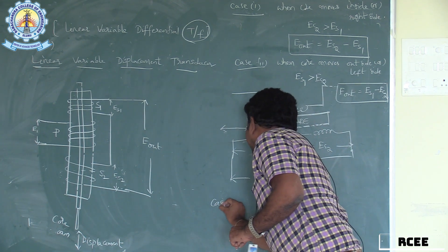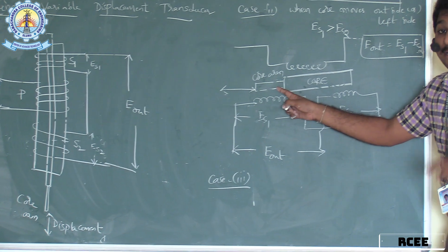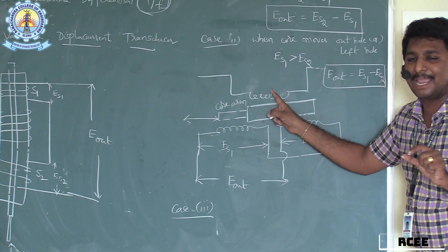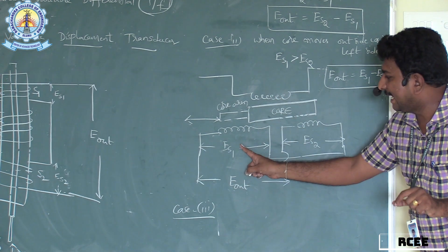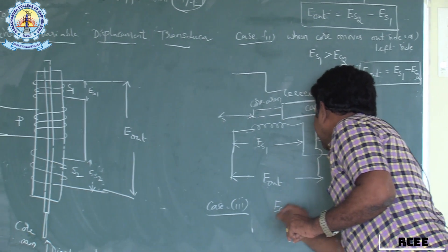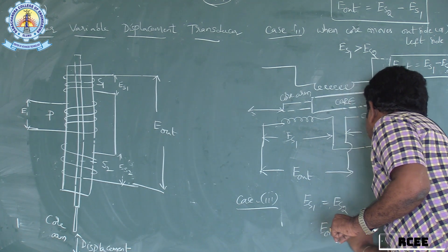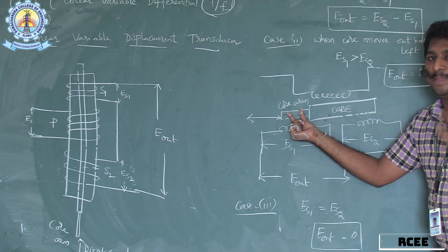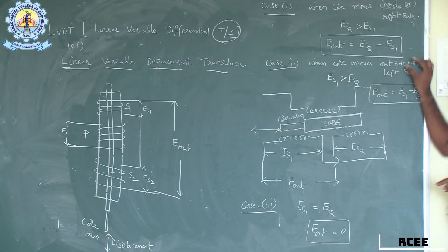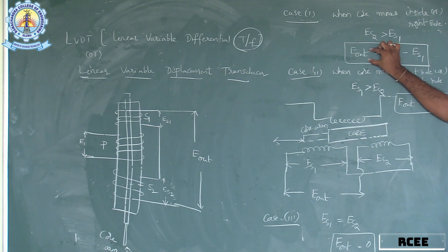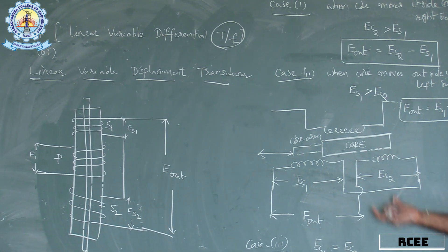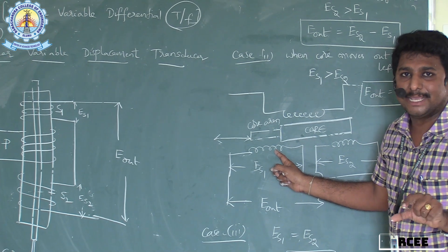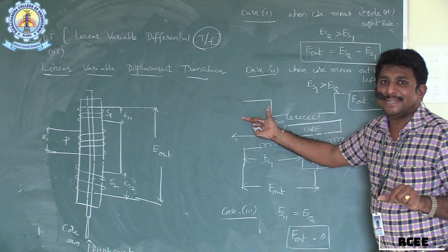Case 3: when the core is at the null position — the equilibrium condition — the flux linkages between the two secondary windings and the primary winding are the same. In this case, ES1 = ES2, therefore Eout = 0. According to the movement or displacement of the core arm, the displacement is converted into a measurable output voltage, which is the electrical parameter. This is how LVDT converts the physical quantity displacement into electrical quantity voltage.